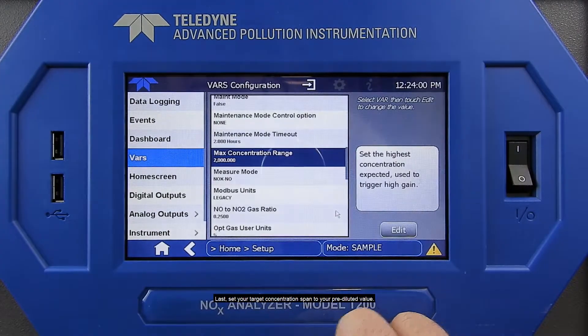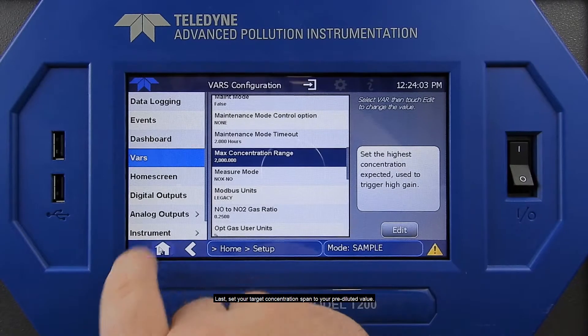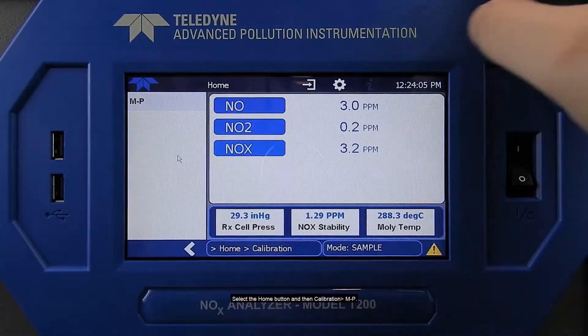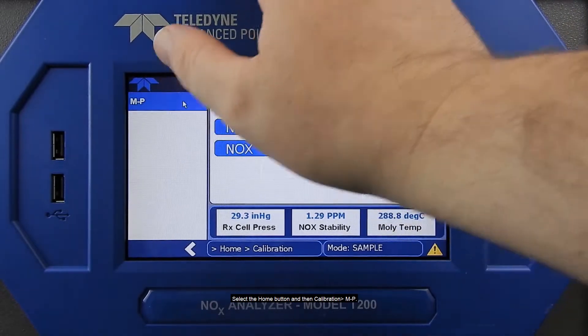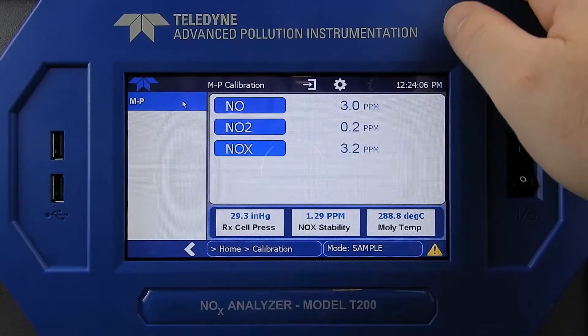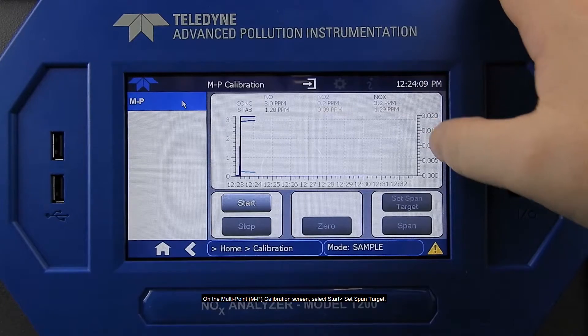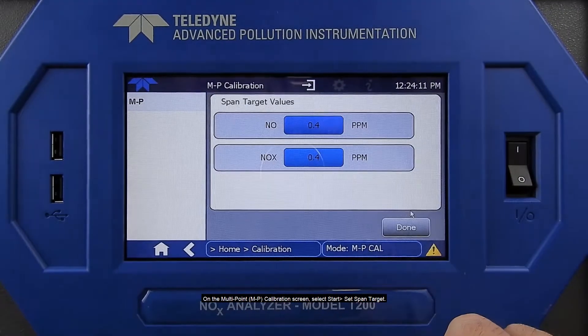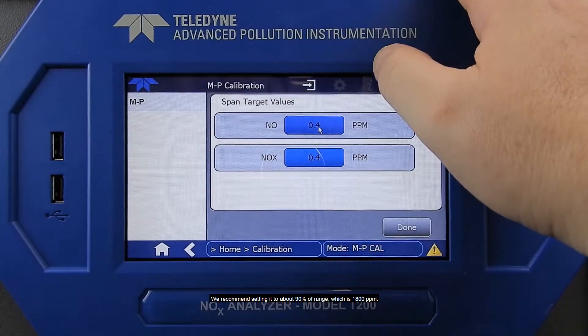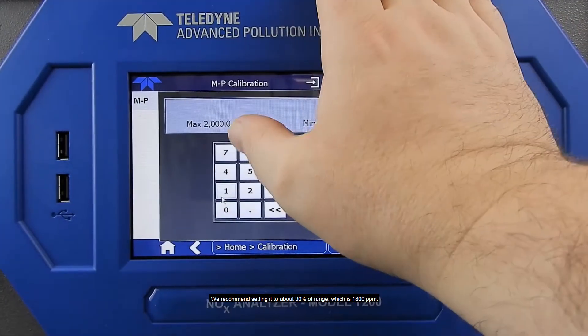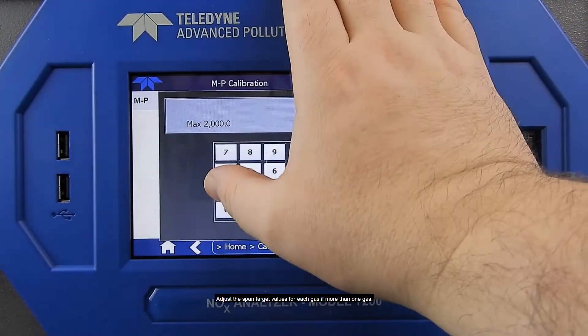Last, set your target concentration span to your pre-diluted value. Select the Home button and then Calibration, MP. On the Multipoint Calibration screen, select Start, Set Span Target. We recommend setting it to about 90% of range, which is 1800 PPM. Adjust the span target values for each gas, if more than one gas.